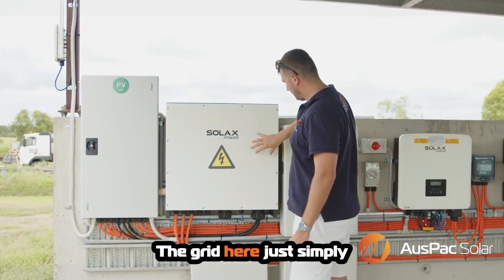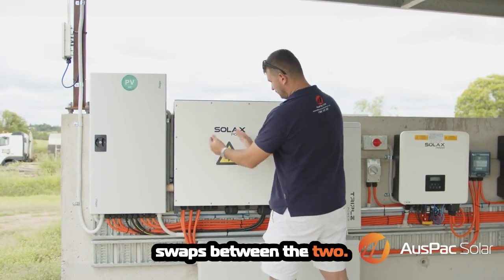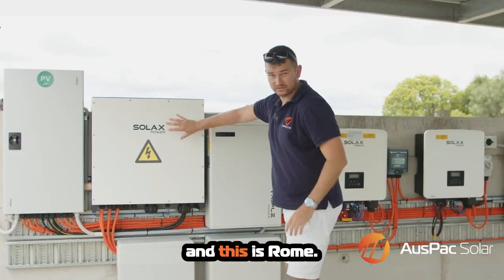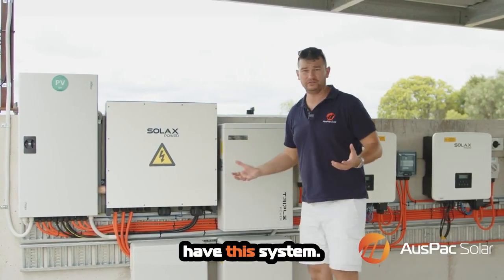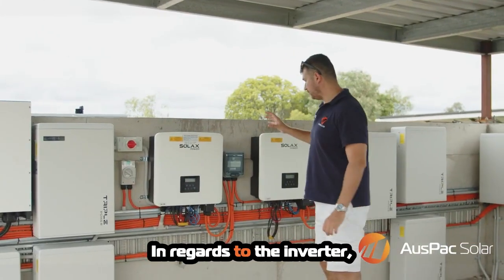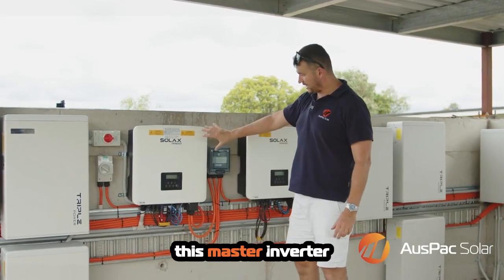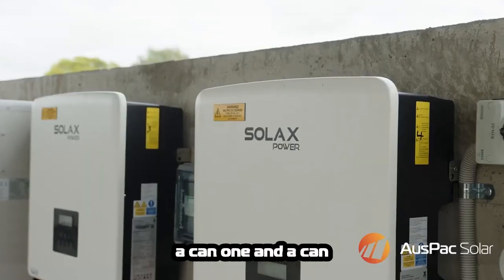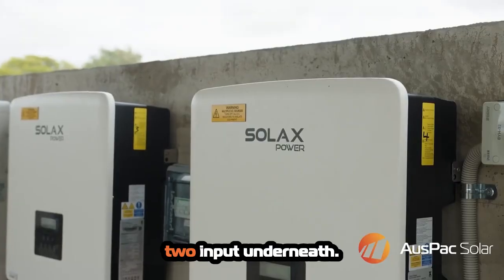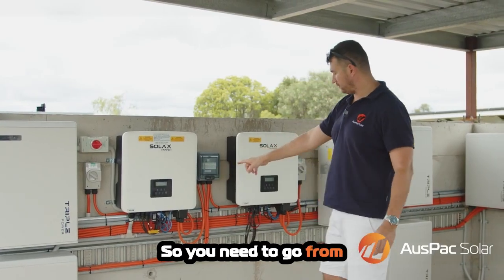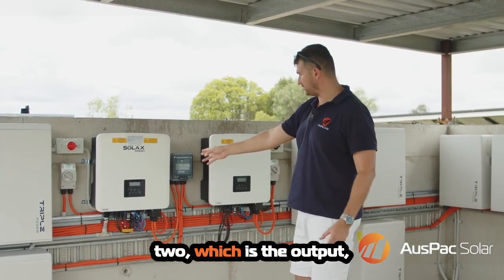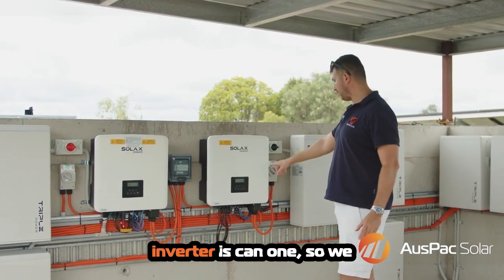The grid here just simply swaps between the two. All roads lead to Rome, and this is Rome. Without this, we wouldn't be able to have this system. In regards to the inverter, this master inverter in particular, we have a CAN 1 and a CAN 2 input underneath. So you need to go from the data cable from CAN 2, which is the output, and the input on each inverter is CAN 1. So we go CAN 2 to CAN 1.